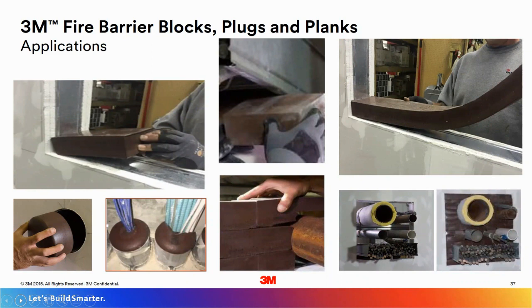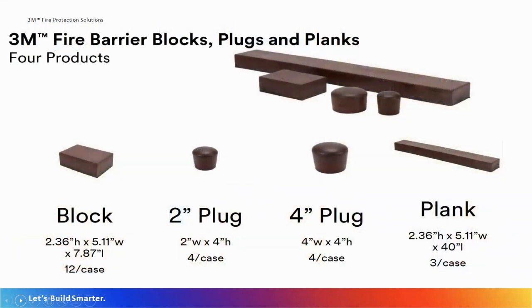The fire barrier plugs in the lower left-hand corner, that's a great product if you have sleeves cast in concrete floors, for example. You can insert the plugs, and then later in the project, you can come back, cut a hole in them, and pull your cable through. These are flexible foam billets, if you will. So if you need to get back into them at some point and run more cable, you can easily cut them with an insulation knife. And again, any gaps or cracks you had, you would fill up with the FIP foam or one of our approved fire stop sealants. Next slide, please. They're available, as I had mentioned, in a few different sizes and configurations. Next slide.